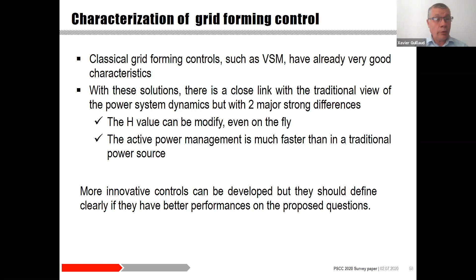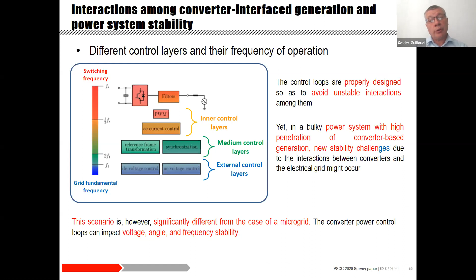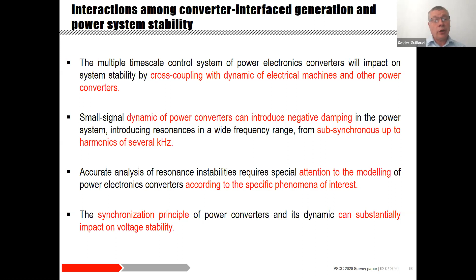Let's conclude now with some words about the interaction among converter interfaced generation and power system stability. This figure records the different layers of control and their frequency of operation. The control loops are properly designed so as to avoid unstable interaction among them. Yet, in a bulk power system with high penetration of power electronics-based generation, new stability issues arise, as an interaction between converters and the electrical grid may occur. The multiple timescale control system of power converters will impact stability by close coupling with dynamic machines and other power converters. Small signal instability of power converters can introduce negative damping in the power system, introducing a resonance in the wide frequency range from subsynchronous up to harmonics of several kilohertz. And the synchronization principle of power converters and their dynamics can substantially impact voltage stability.